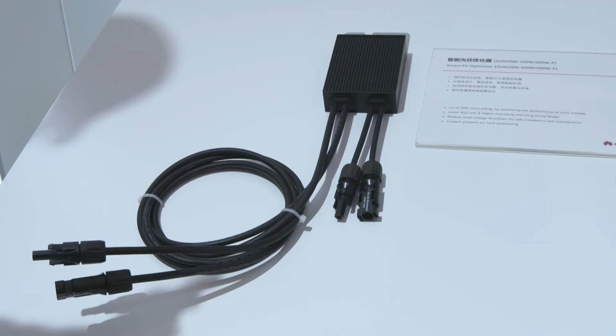So in this case, when the modules are equipped with optimizers, only the panels in the shadows are affected. The other modules can still work at their highest power points. And also the Huawei inverters support intelligent arc protection and automatically shut down within 0.5 seconds. And also we can see this kind of chart.